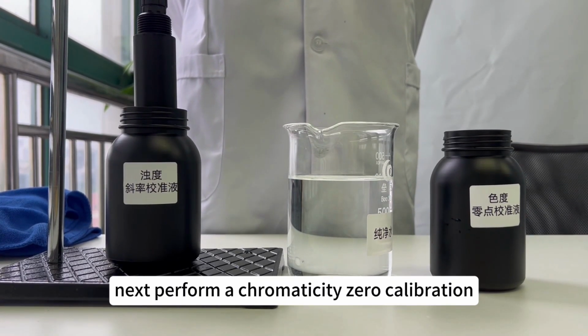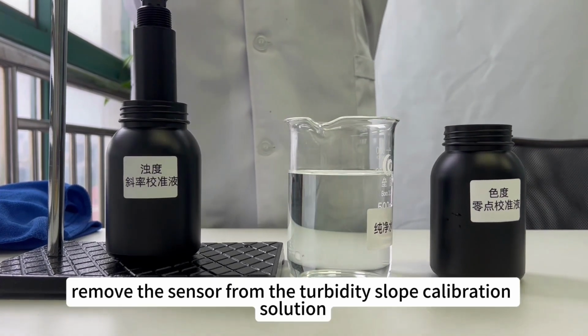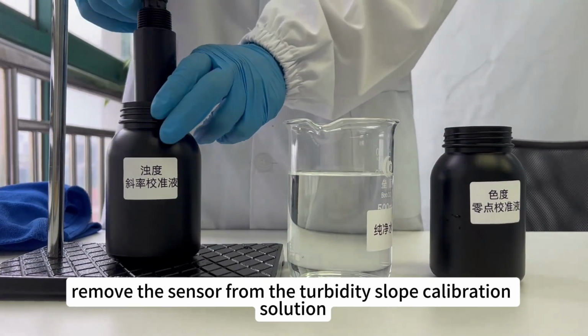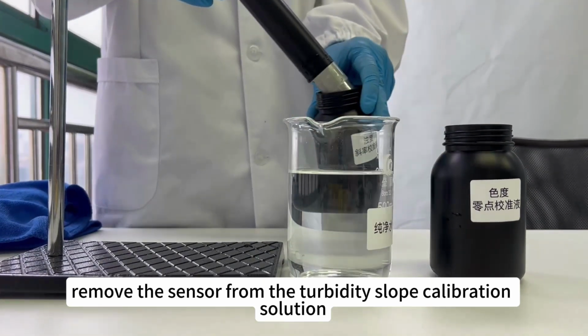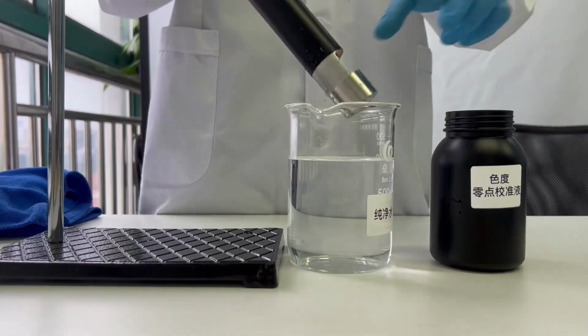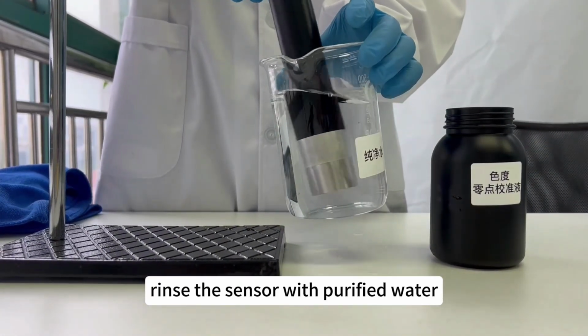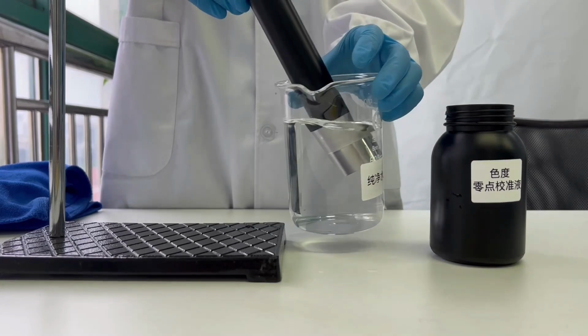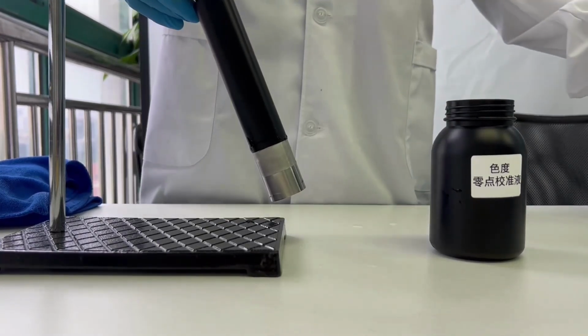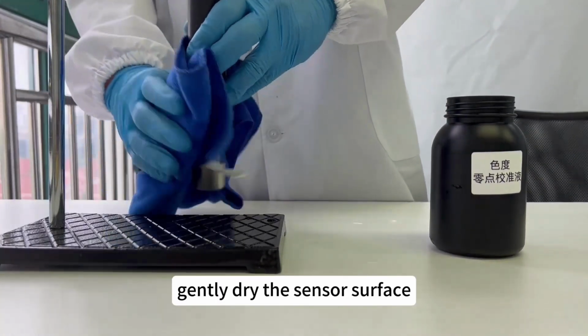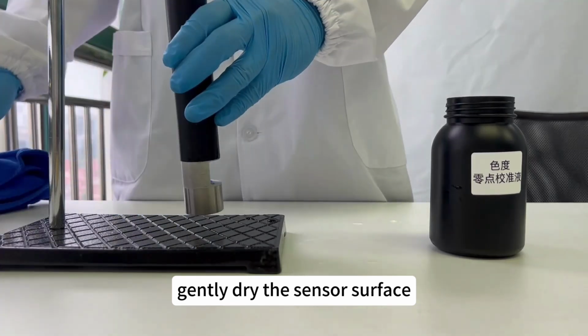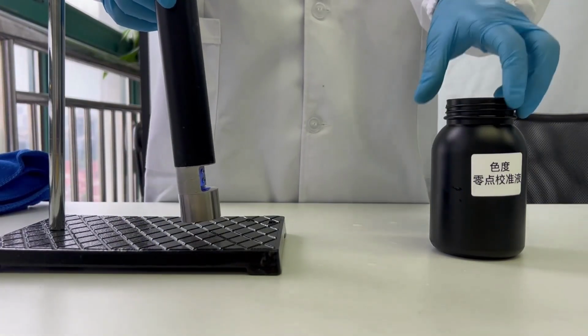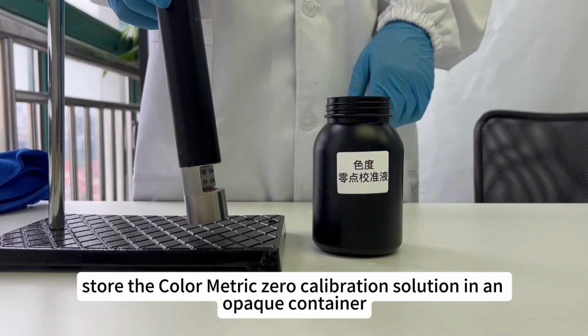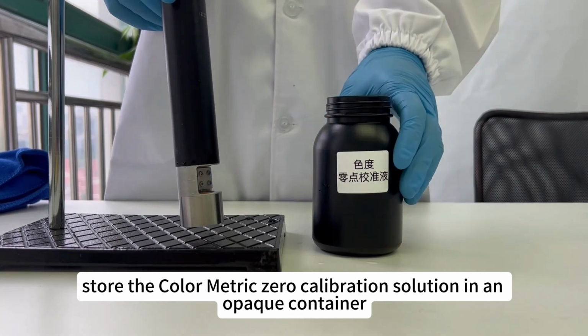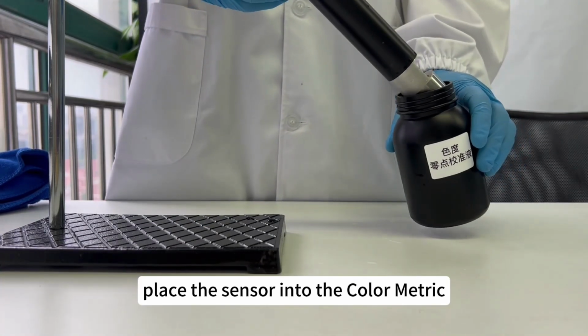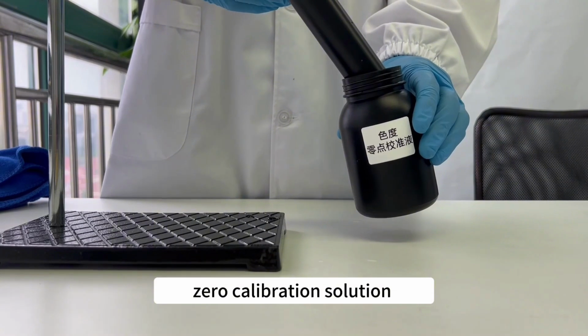Next, perform a chromaticity zero calibration. Remove the sensor from the turbidity slope calibration solution. Rinse the sensor with purified water. Gently dry the sensor surface. Store the Colorimetric Zero calibration solution in an opaque container. Place the sensor into the Colorimetric Zero calibration solution.